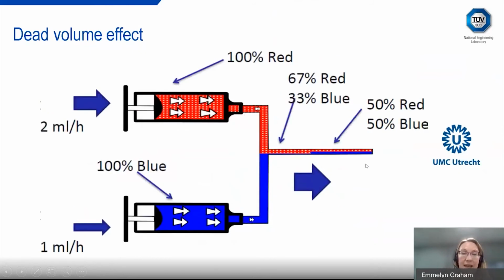If we then increase the flow rate in the red, which we'll double to 2 milliliters per hour, what happens, after we have the compliance issues and other things happening, is that when we go into the infusion line going to the patient, initially it was 50% red, 50% blue. We've then doubled the flow rate, so it's now 67% red, 33% blue.